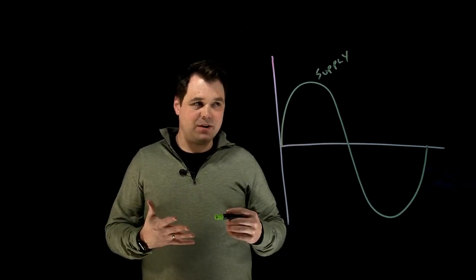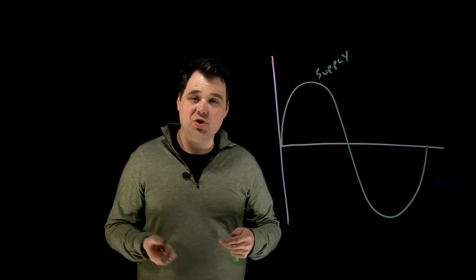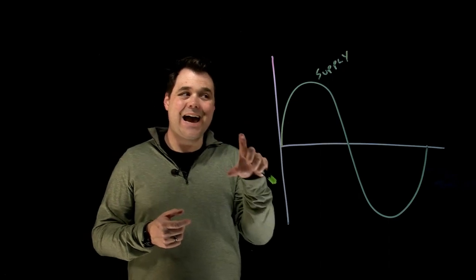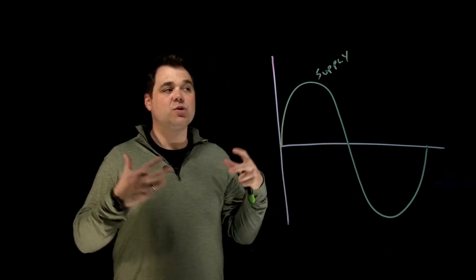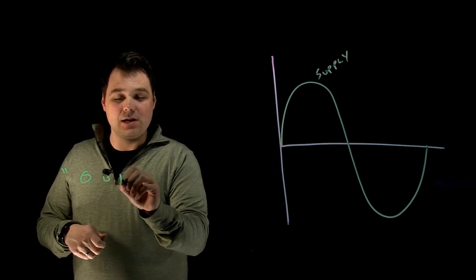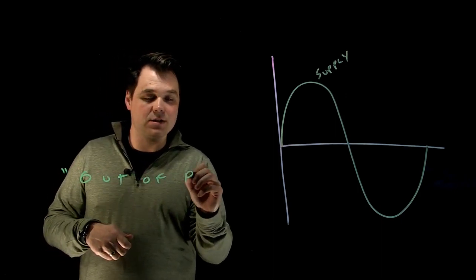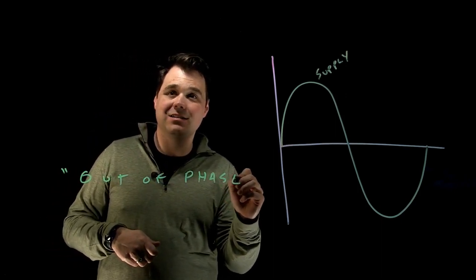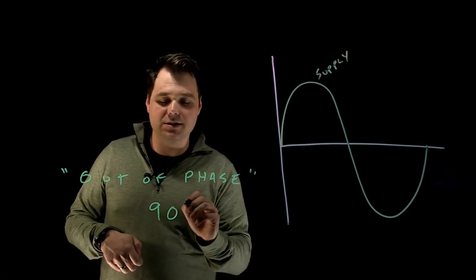Now, how do we fix that? Well, the shading coil, as you saw, was actually installed at a 90 degree angle. So it's out of phase with the supply flux, out of phase by 90 degrees. 90 degrees is the key there.